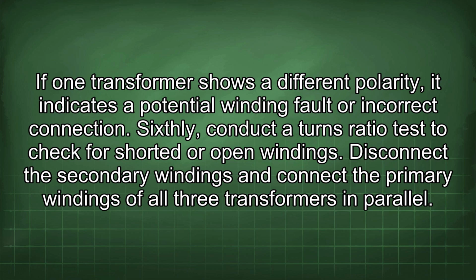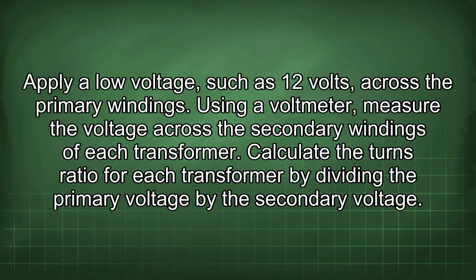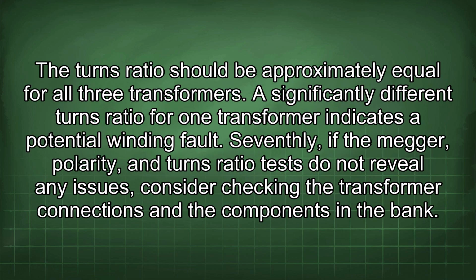Sixthly, conduct a turns ratio test to check for shorted or open windings. Disconnect the secondary windings and connect the primary windings of all 3 transformers in parallel. Apply a low voltage, such as 12 volts, across the primary windings. Using a voltmeter, measure the voltage across the secondary windings of each transformer. Calculate the turns ratio for each transformer by dividing the primary voltage by the secondary voltage. The turns ratio should be approximately equal for all 3 transformers. A significantly different turns ratio for one transformer indicates a potential winding fault.